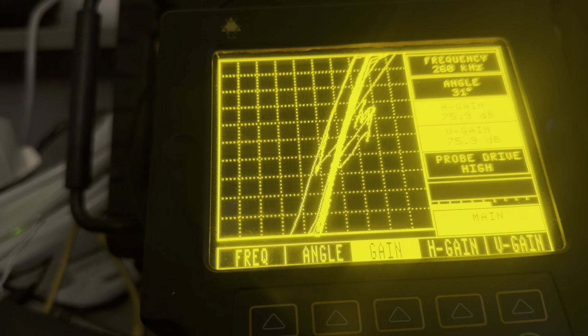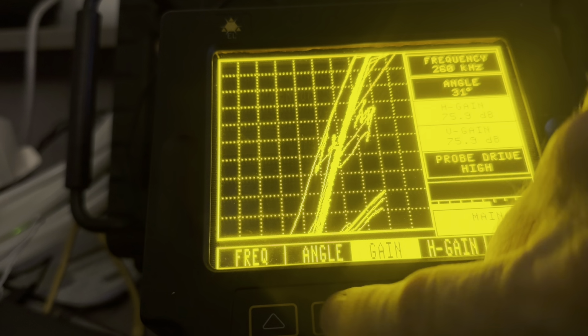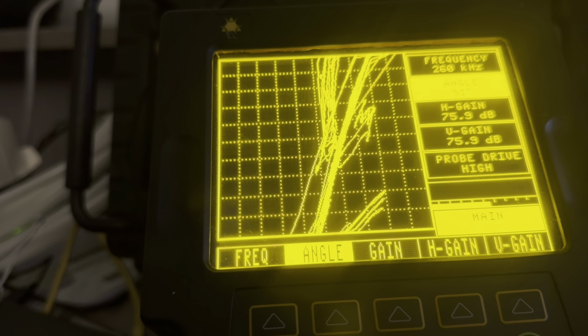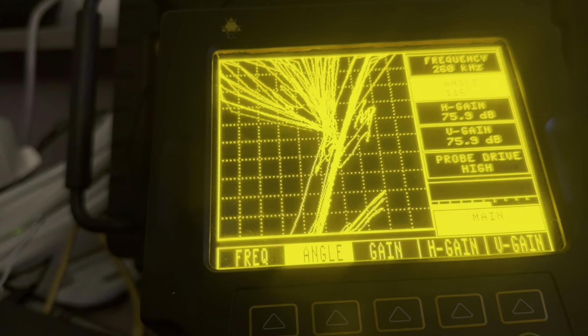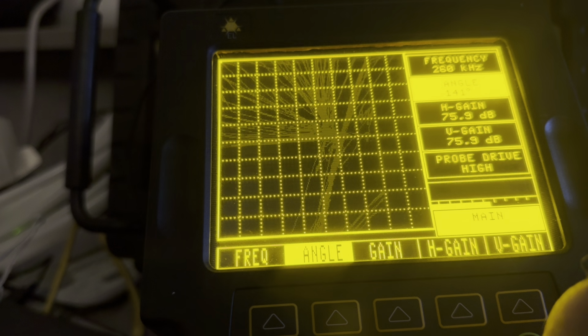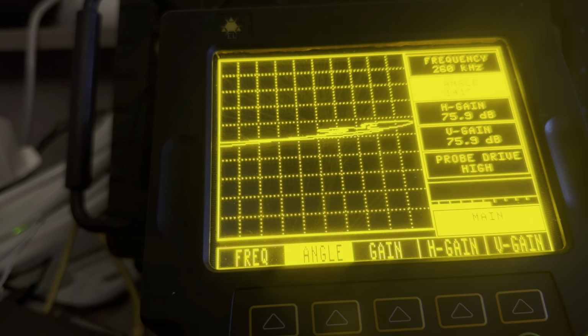So now if I scan my material, getting some action, I'm going to null it again. And then I'm going to adjust the angle. So we're going to adjust liftoff. Now this one has a lot of liftoff because this is not a differential arrangement. So if my impedance point goes to the left when I lift off, the phase is set correctly. So now I'm back on the material. I always like to hit null, just for the heck of it. Hit erase.